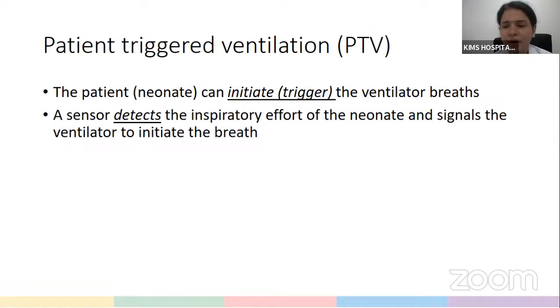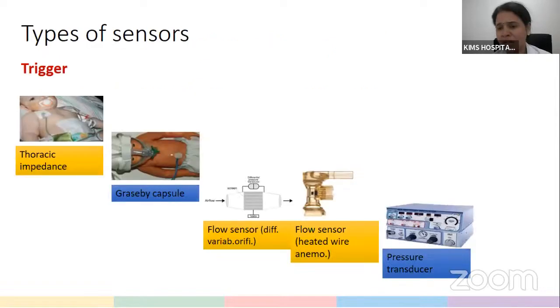So it is definitely wiser and more reasonable to resort to patient-triggered modes of ventilation, where the signal from the neonate that indicates the patient has initiated a breath can be sensed by the ventilator, and the ventilator delivers an inspiratory breath which is synchronized to the patient. This sensor detects the inspiratory effort of the neonate and signals the ventilator to initiate a breath.